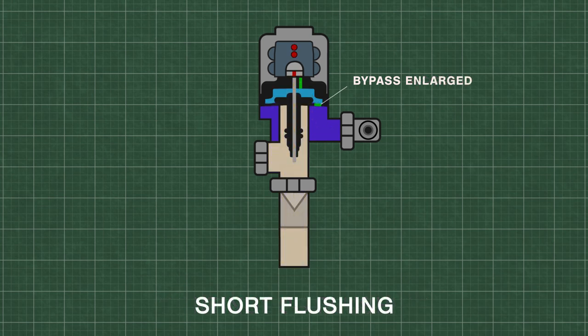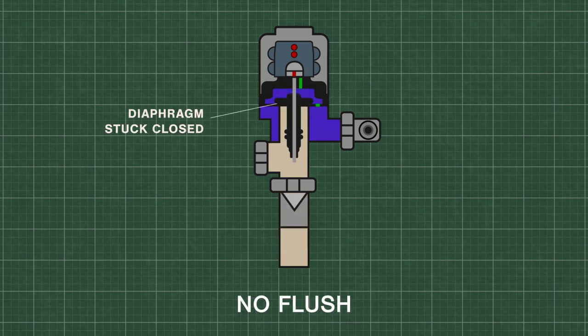If the bypass hole is enlarged, then the upper chamber will fill with water too quickly. Alternatively, if the diaphragm or relief valve is worn down or sticks to the valve, it can prevent the unit from even functioning at all.